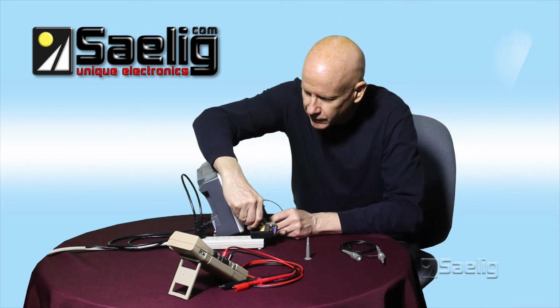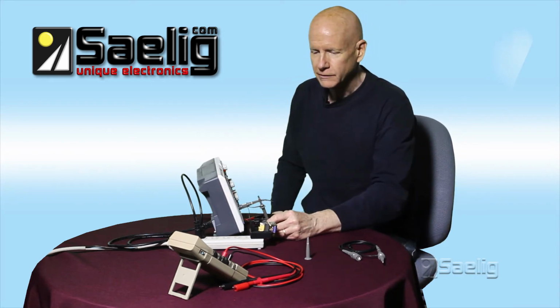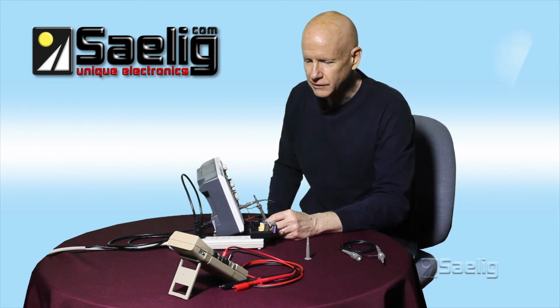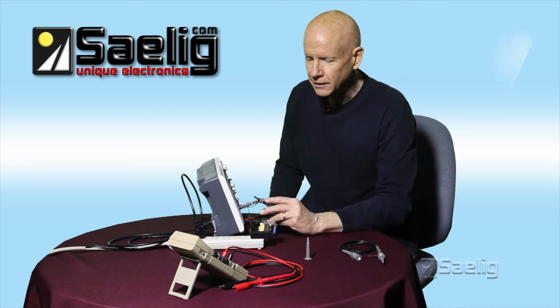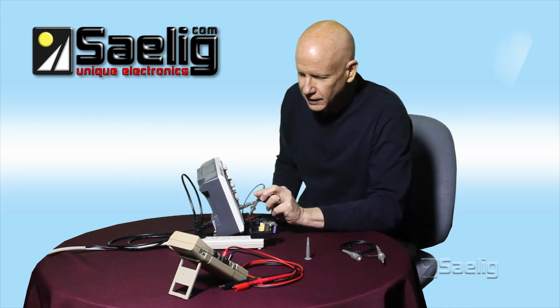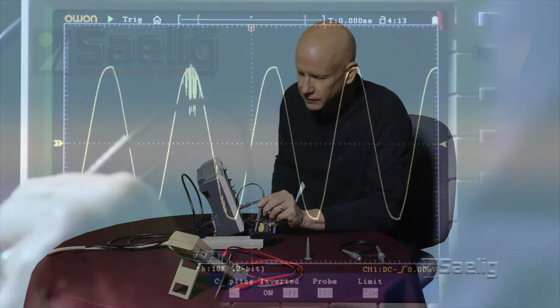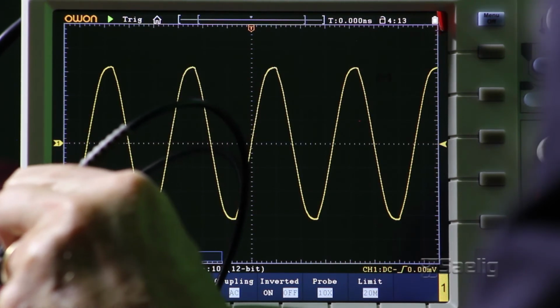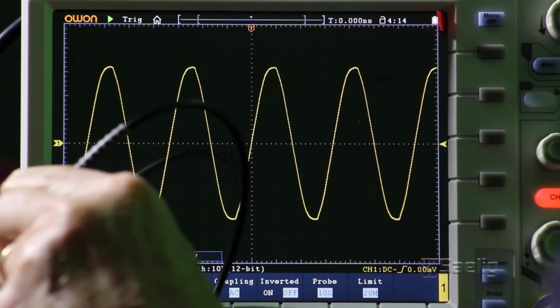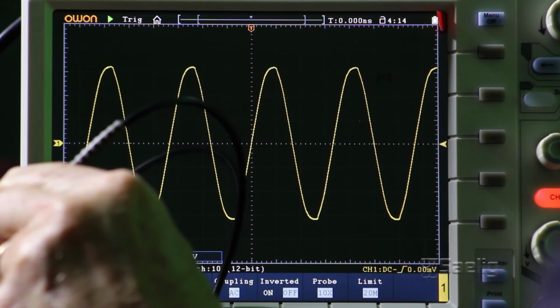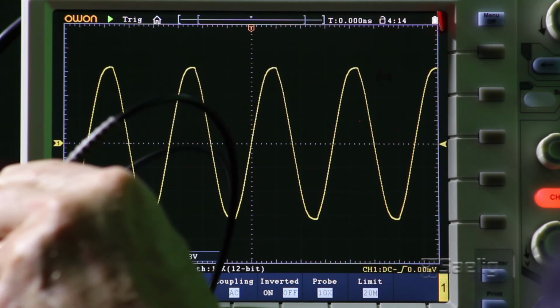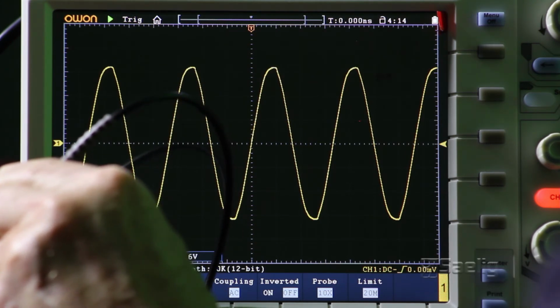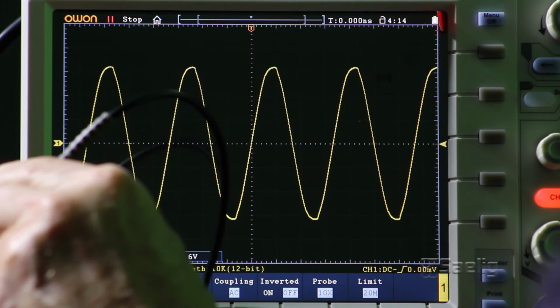Okay, so I'm going to hook up my ground to the neutral. Since this little transformer here doesn't even have a ground, I'm going to then probe the hot with this probe here set on times 10. Okay, and you can see that I get a nice waveform here. You can see the distortion, and considering all the reactive loads that are attached to your local transformer, it's not surprising to see some distortion on the waveform. Okay, we're going to just press the stop button here.